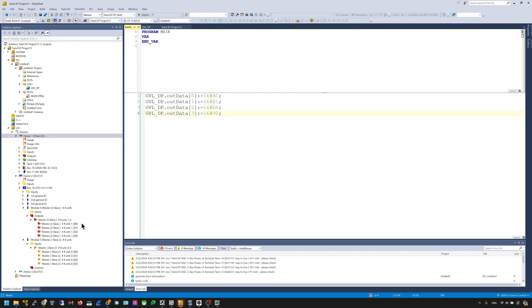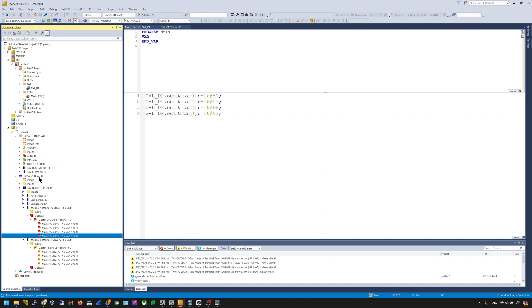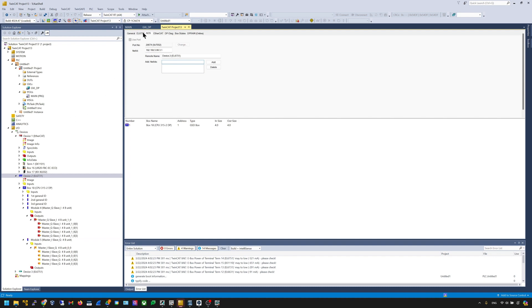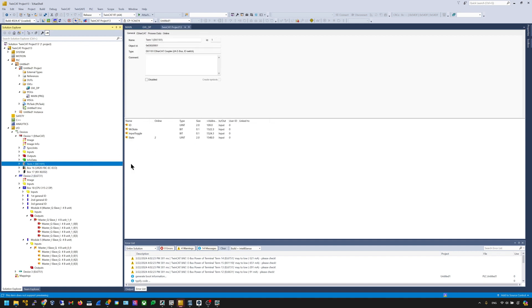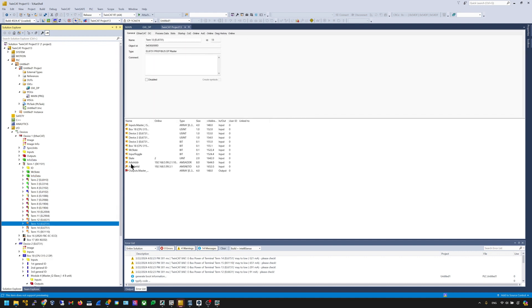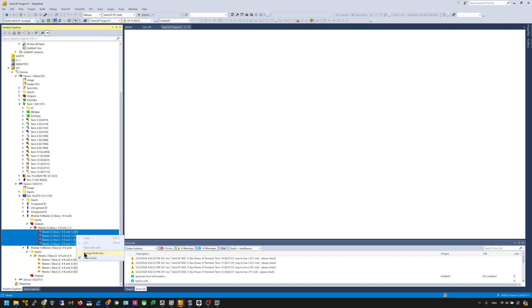Go to Build and select Build Solution to compile the project. Then map the process variables. Go to the EL6731 device, click the Profibus module, and under the EL6731 tab press Search — this finds which terminal can act as the Profibus master. In my system it's Terminal 13 inside EK1101. Make sure you select the correct module, otherwise you'll get an error on download. Select all the data, right-click, Change Multiple Links, and choose the variables defined in your GVL. Do the same for the input variables.